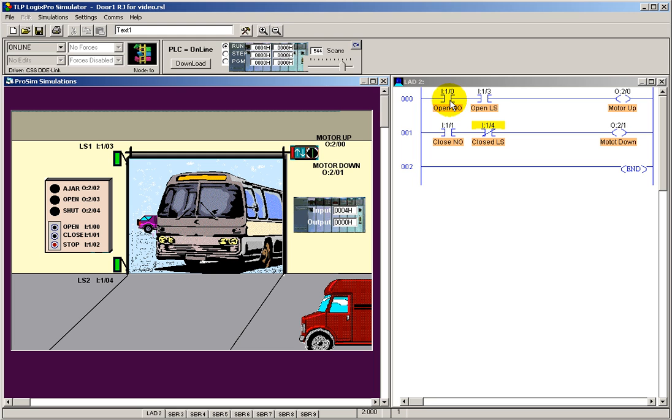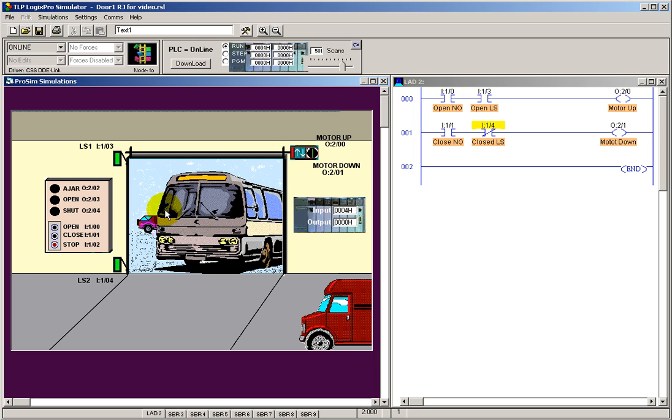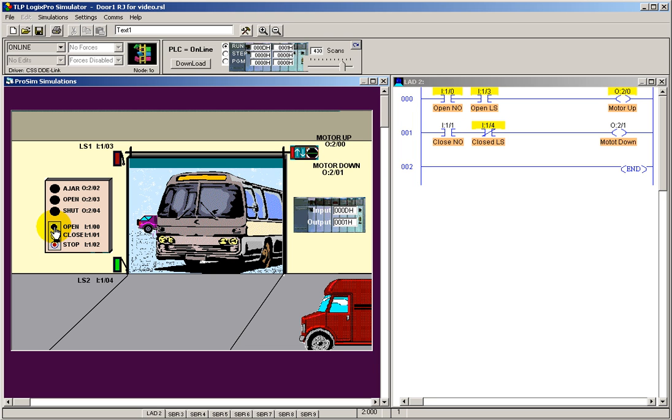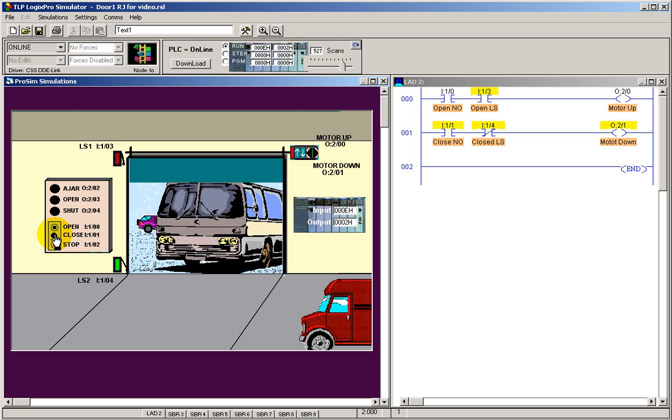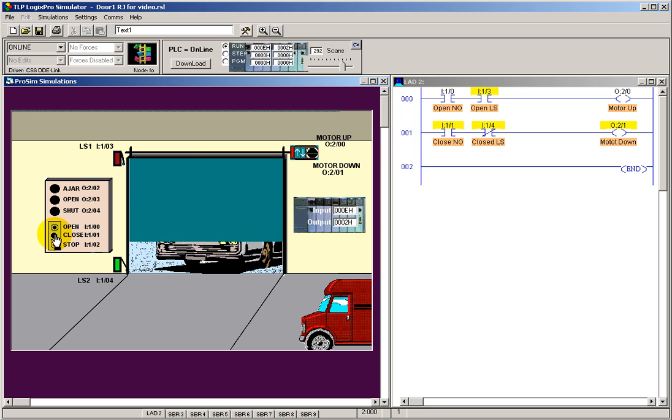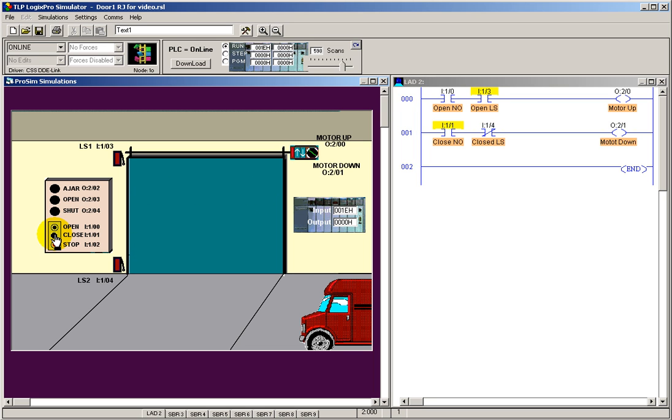And it says examine if closed to allow it to open again. Well, it is no longer closed. This statement is false. So I can hit open. And even though I've got a true statement here on my open switch, I won't energize because the open limit switch is open, and it needs to be closed to be true here. So we've now prevented over travel, and we're no longer burning up our motor by stalling the motor.